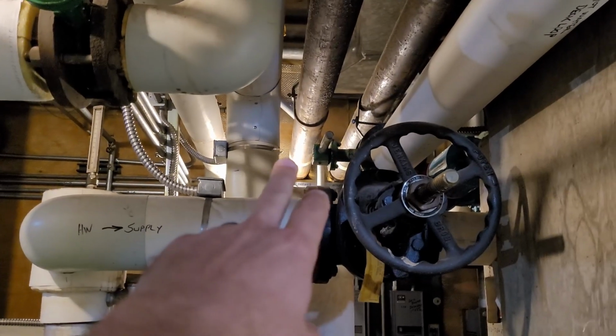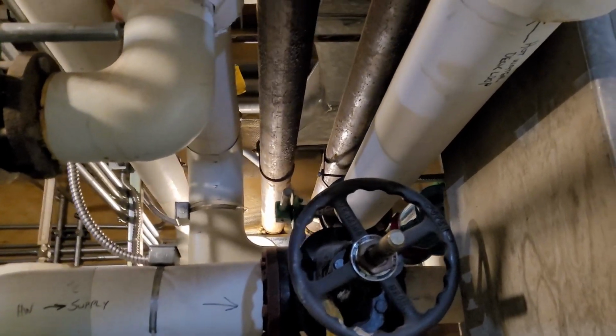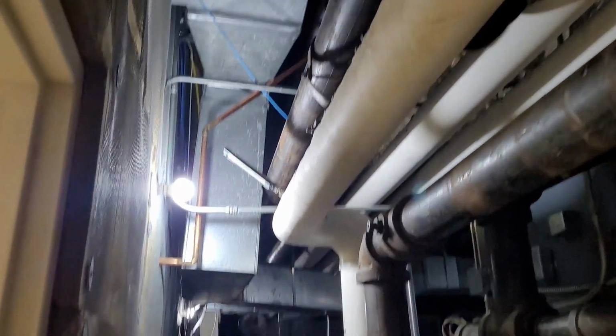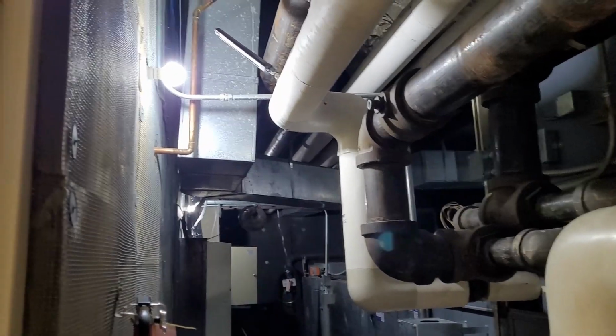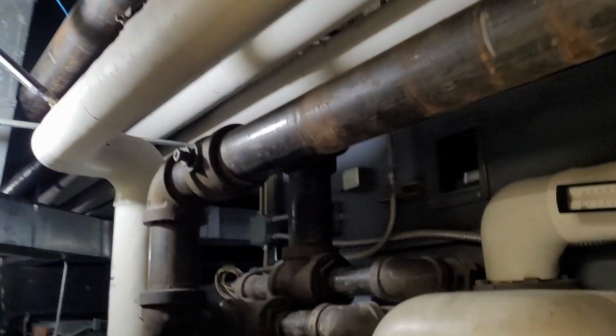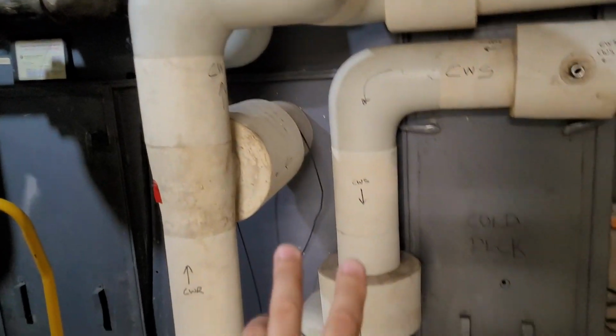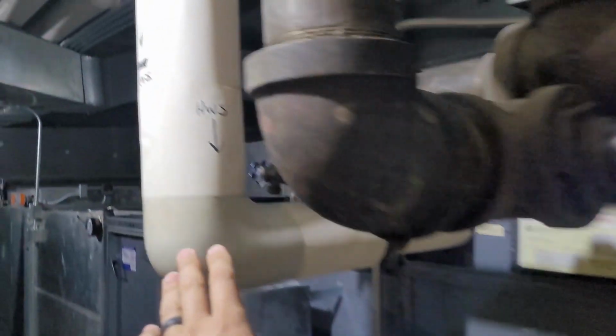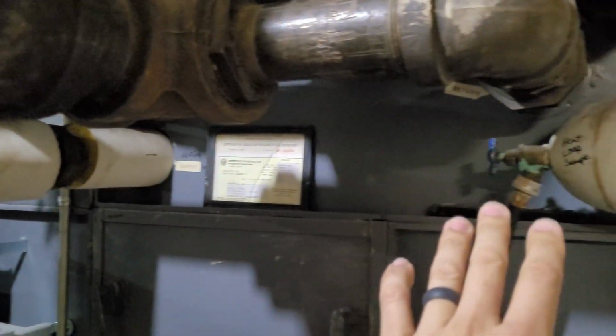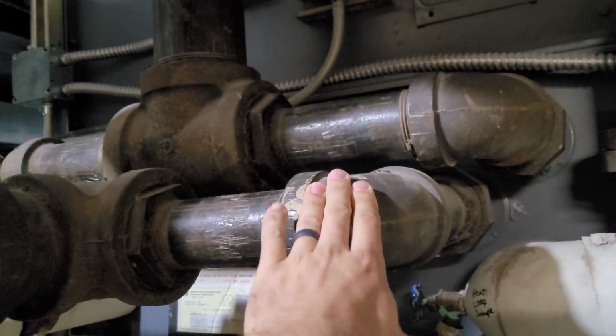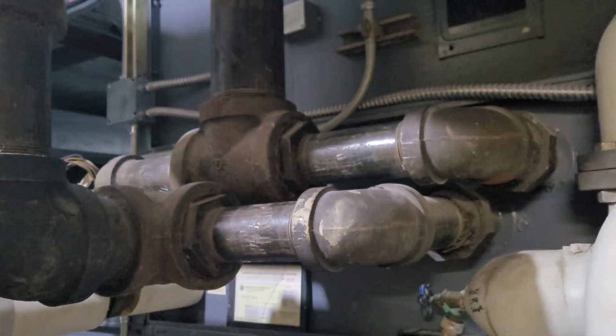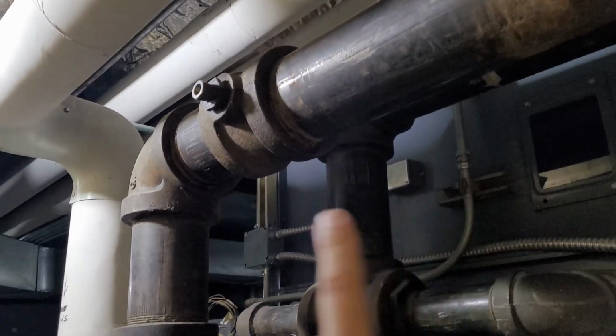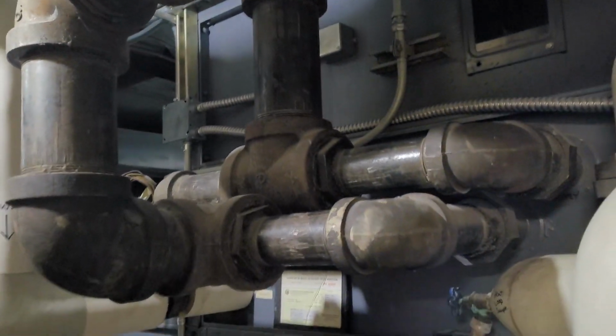So here we are on the other side of the wall. The condenser lines come through, the condenser water comes through. Now there is a cooling tower on the roof, and so they continue that way, and then they turn and go up following that wall, but also they go here. So this is a multi-zone unit, and you have chill water on the cold deck, you have hot water on the hot deck, and then you also have these uninsulated pipes, which was my first clue that that might be condenser water.